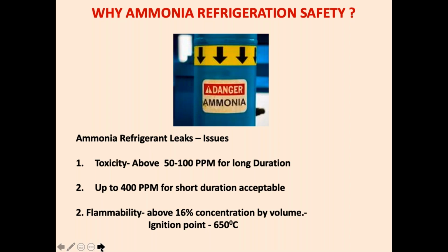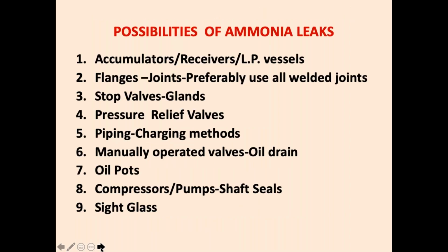Now, flammability, yes, is an issue, but only above 16% concentration, and the ignition point, as I mentioned, is 650 degrees centigrade. So it is not in reality a big issue. I had shown in my ammonia presentation that no ammonia equipment requires flame-proof equipment. Standard equipment is good enough. Now, where does the possibility of an ammonia leak exist? We are going to talk only about the toxicity issue, not the flammability issue, and toxicity will take place only when ammonia leaks.